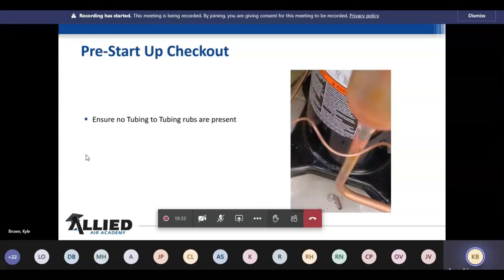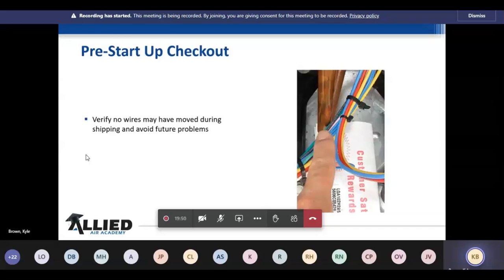And I realize that's time consuming, but think about the repercussions of not doing it. You put a 25-ton unit on the roof and it's got issues, taking that back down and putting it back up is a huge deal. It's not really fun to do. So here, we also want to make sure there's no wires touching anything. This happens to be the discharge tube, and you can see this is a unit that was from 2006. So there's been a lot of changes in quality and stuff like that, but this can still happen. I mean, these things are put together by people, so we have to inspect it.